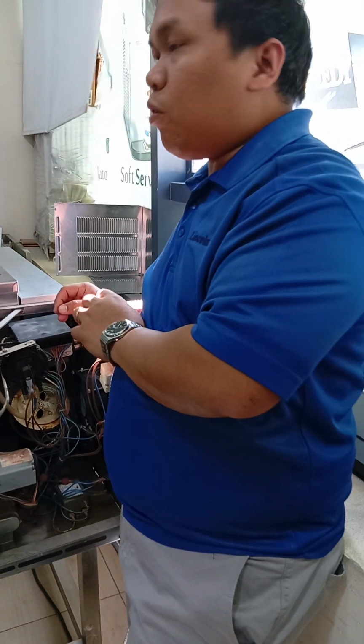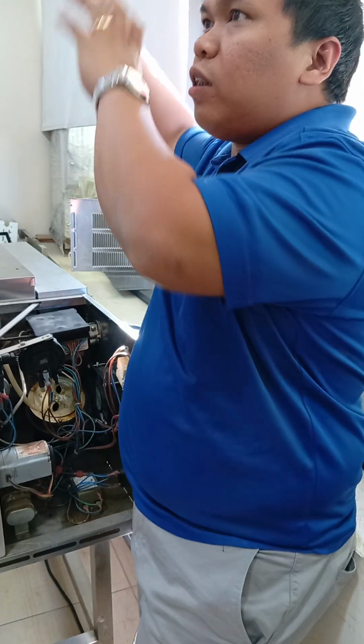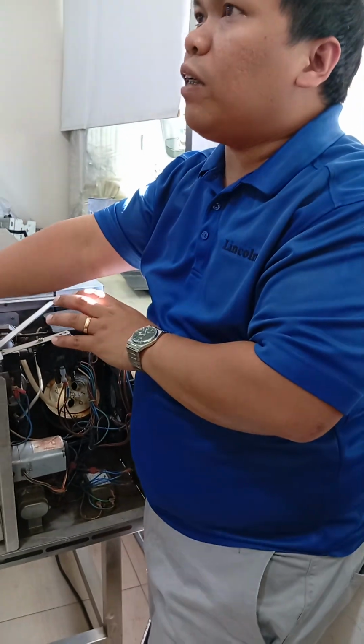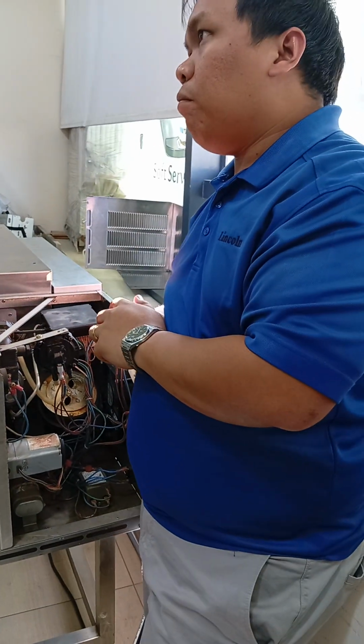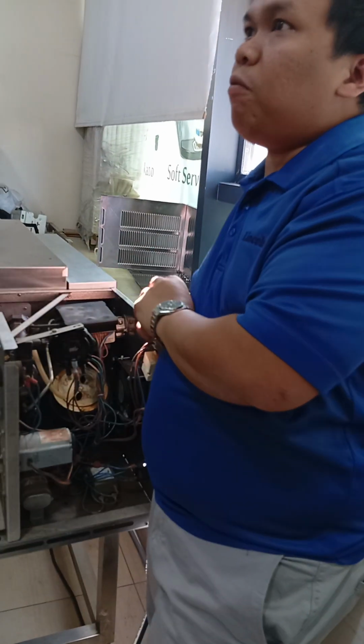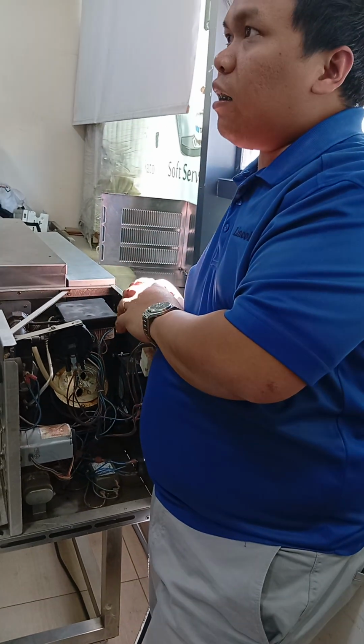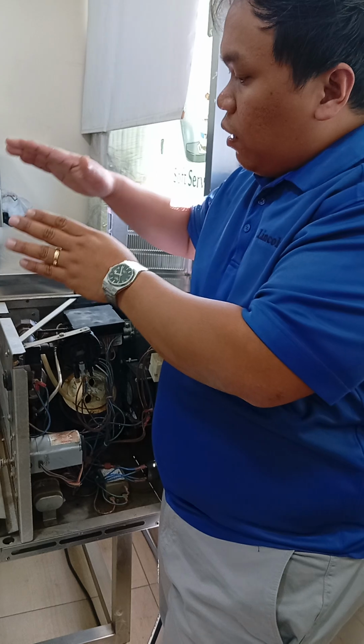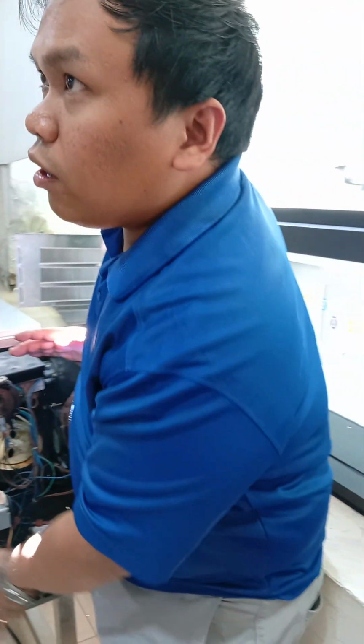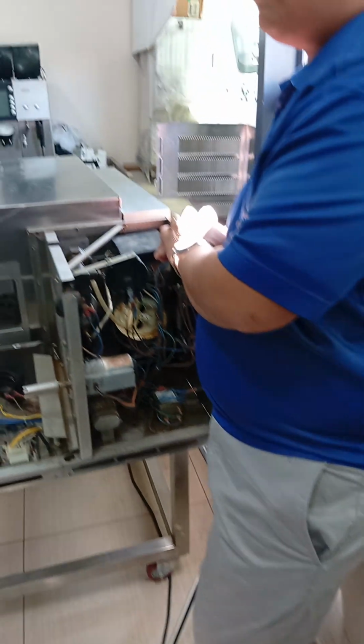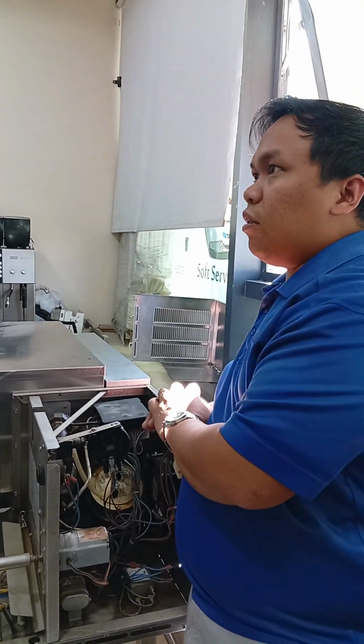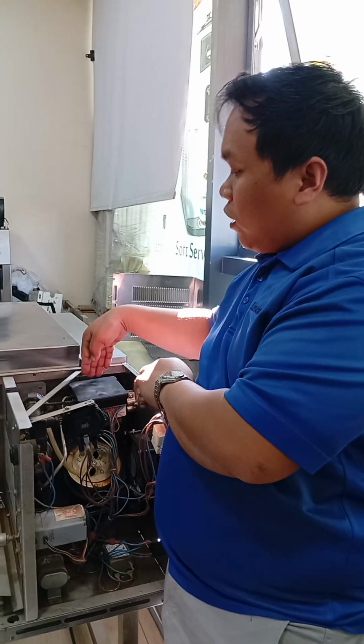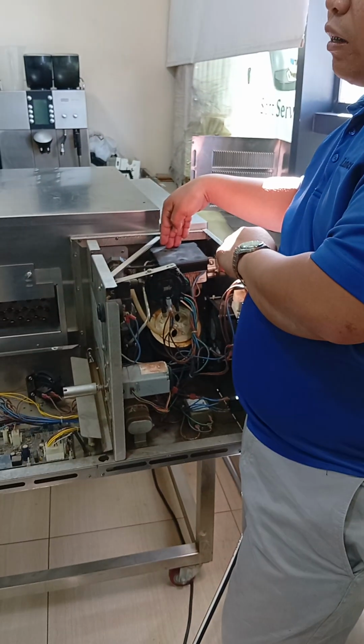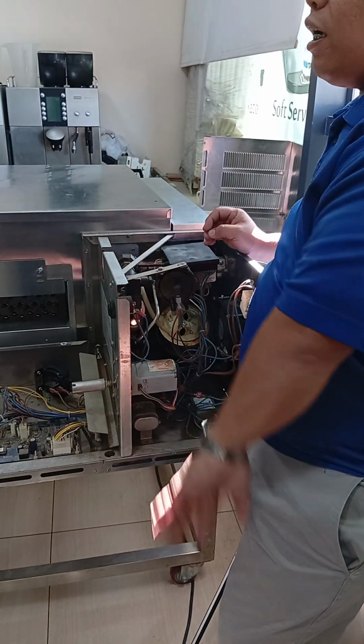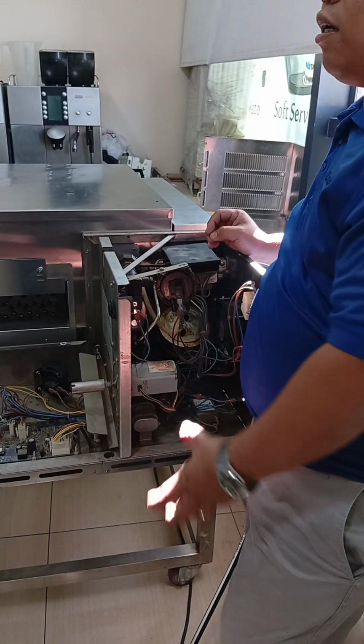Because instead of proper extraction sucking all the heat and some of the grease coming from the pizza, it will stay, because we have a cooling fan. This can stay inside. Because on the machine we have some ventilation in the cover just to suck some fresh air. So if you notice, the cooling fan should not be blowing here, it should suck the air.